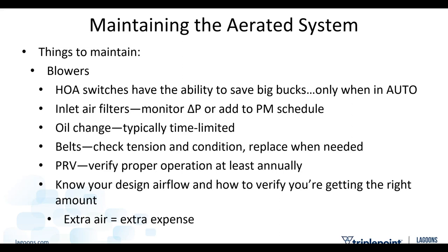If you've got it running in hand, you're missing out on the energy efficiency that you could be realizing with your system. Inlet air filters. I tell people, monitor your pressure change, your delta P across that filter media. When it hits the manufacturer's recommended max delta P, pull that media, stick a new filter in there. That's the way to do it as best you possibly can.